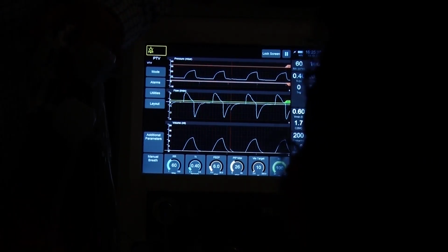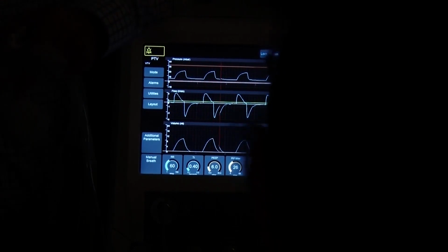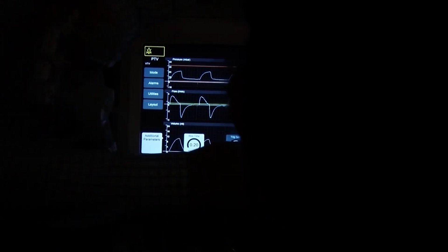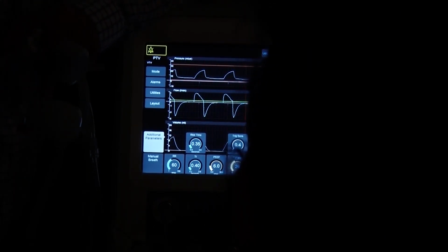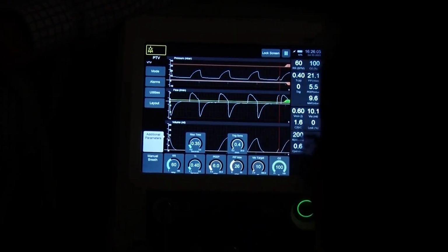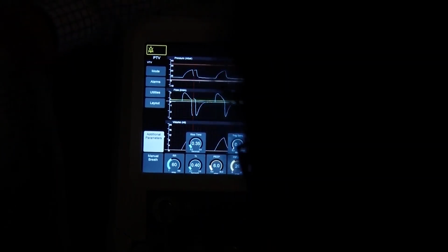Exactly. And this is the other problem. If you go really, really slow in your flow and have a slow rise time, the baby has to work harder to get the breath in. So there's going to be a sweet balance point between that. So if you are going to go very slow, and we do that here, now you can see that our rise time's gone right down, and we've got a very smooth, flat curved wave. The baby's going to have to work harder during inflation. So if you're seeing an increased work of breathing, then you need to go back again.